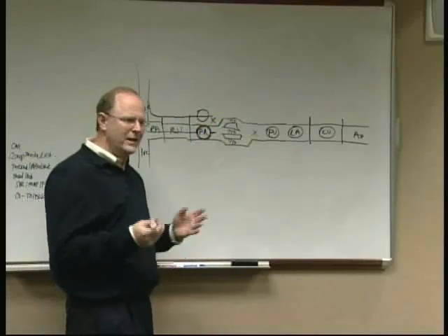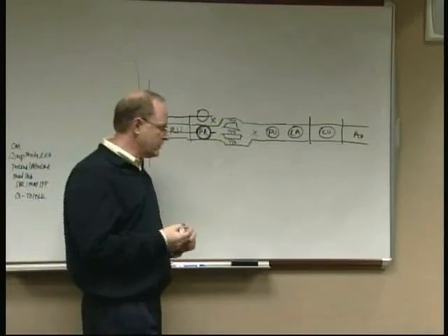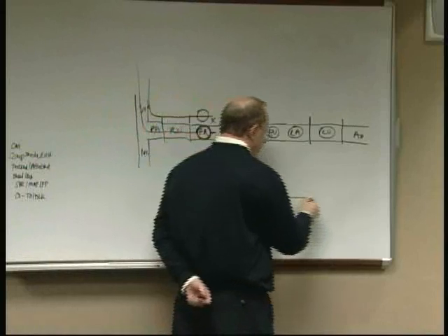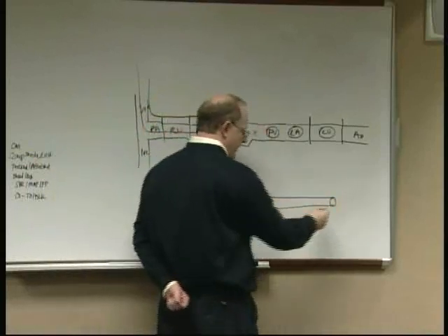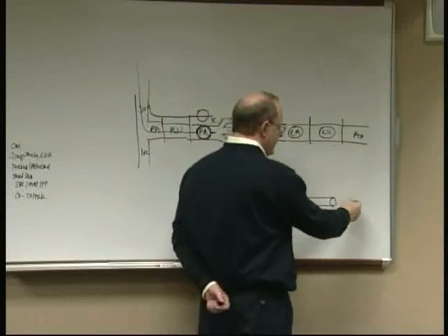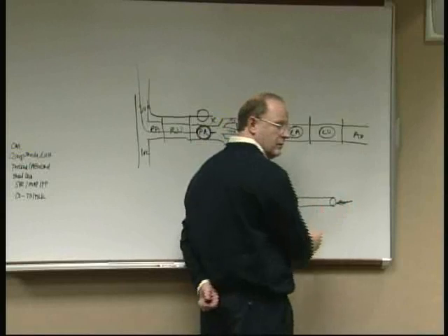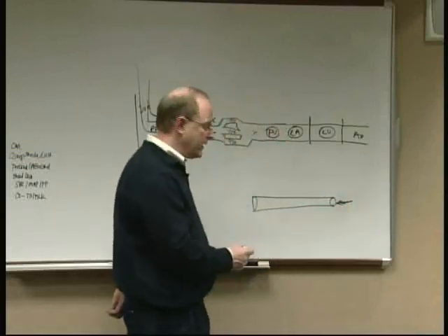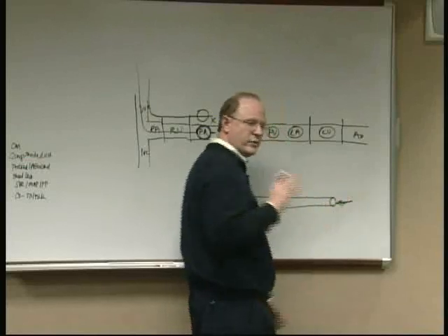And this is a fluid-filled catheter. How does a fluid-filled catheter measure blood pressure? If I take a hollow catheter, and it's full of fluid, and there's a blood pressure where I'm measuring, it pushes pressure on this end of the fluid column, which transmits that pressure along the fluid column.